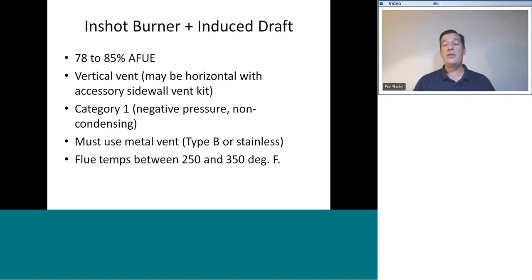When the furnace is at 78 to 85% AFUE, that vent will be vertical. It will be the same vent that the natural draft furnace had, except it might be a bit of a smaller diameter, according to the venting tables. Why? Because we don't have that extra 15 cubic feet per foot of dilution air going up that flue. So those vents can actually be smaller when they serve an induced draft or fan-assisted appliance. You look at the GAMA table, that's known as a fan-assisted draft appliance.